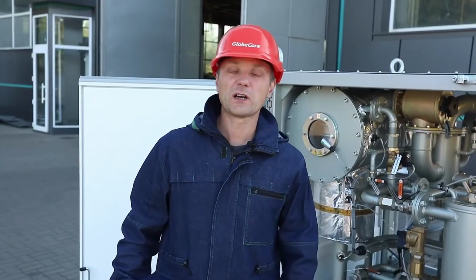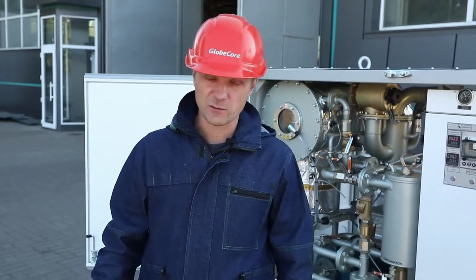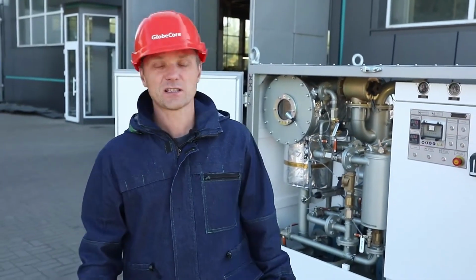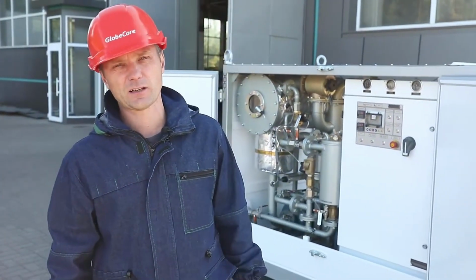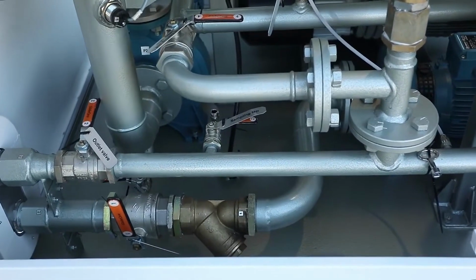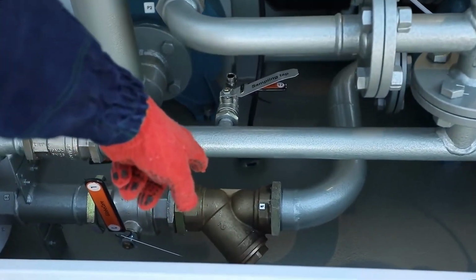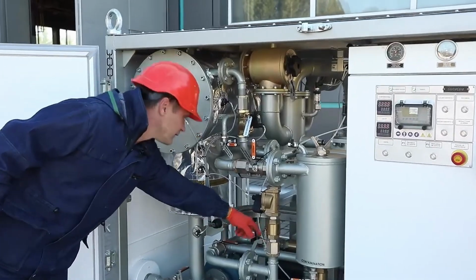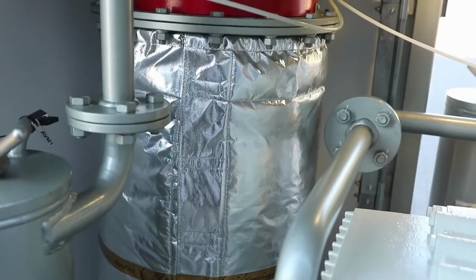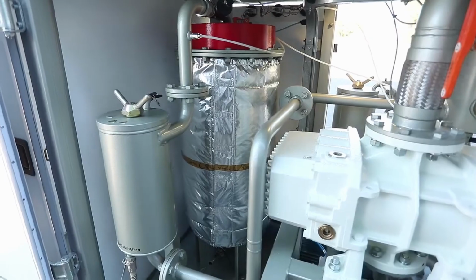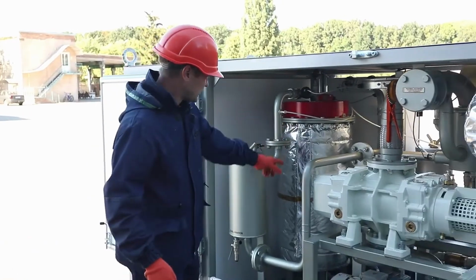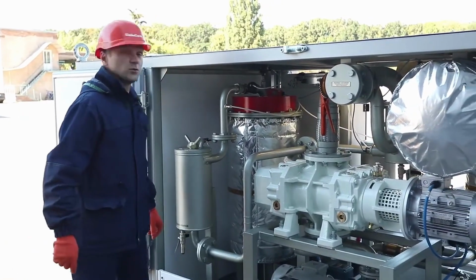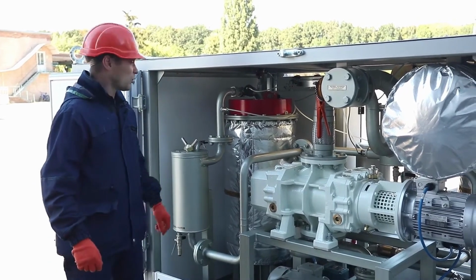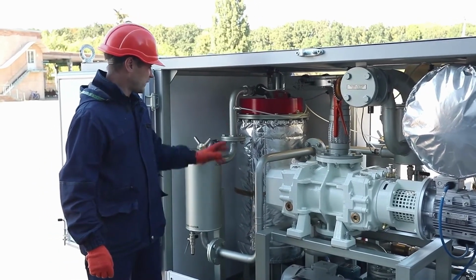The unit is multifunctional and operates in several modes. The main modes include degassing, drying, and filtration of transformer oil. In this mode, the oil is fed by means of an input pump, through a 200-micron mesh filter into a tape heater that increases the oil temperature up to 50-55 degrees. The tape heater has a low heat capacity and a low surface heating power. For this reason, oil overheating is avoided in the event of emergency shutdowns.